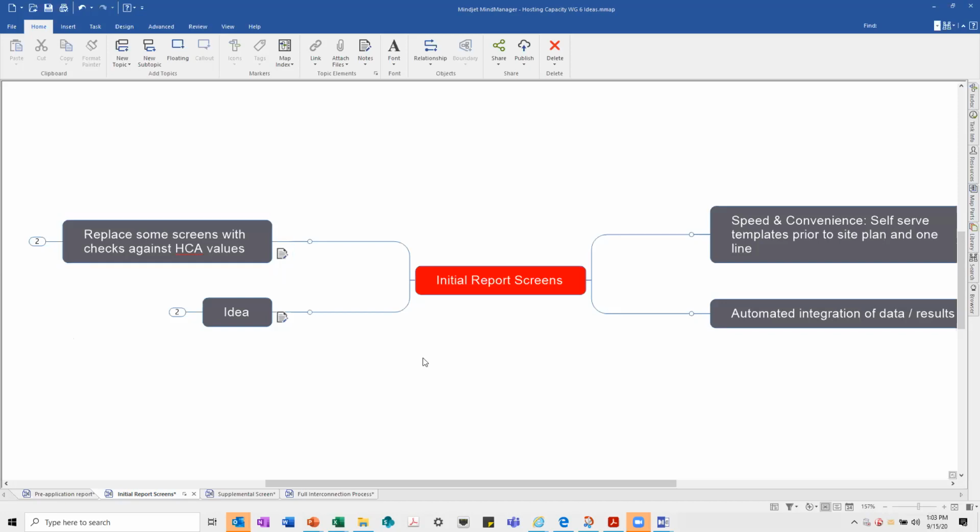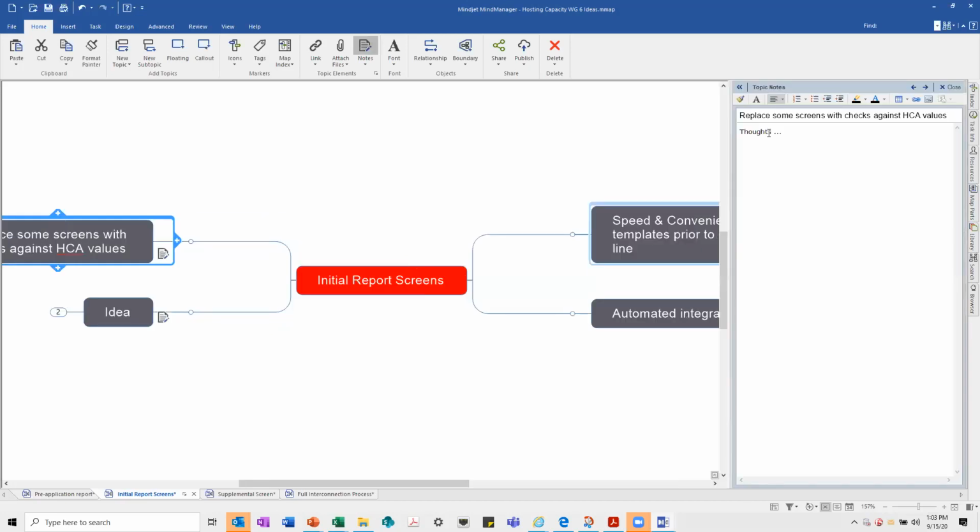So if I understand what IREC is saying, then you guys are hoping that part of the integration with hosting capacity, these capabilities that we're looking at, you would like that hosting capacity to have the 15% screen, so that you can go to the map and then evaluate whether there's 15% penetration or higher. This is Brian. No, not quite. That basically that screen would be replaced with a reference to the HCA values, assuming that the HCA values and how they're determined is actually a better representation of the system than the 15% number. So the HCA values, isn't that just how much hosting capacity is available? Isn't that something we already show? Right, yeah, so this would be an improvement to the screening process, not to the HCA that I'm referencing.